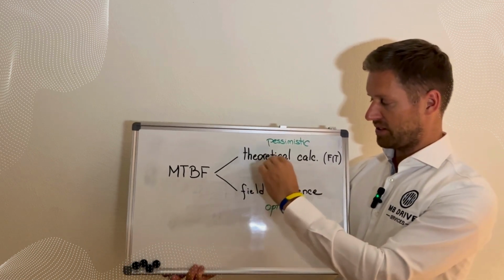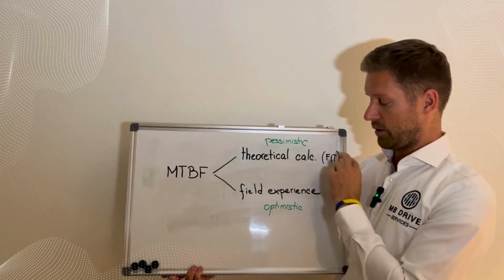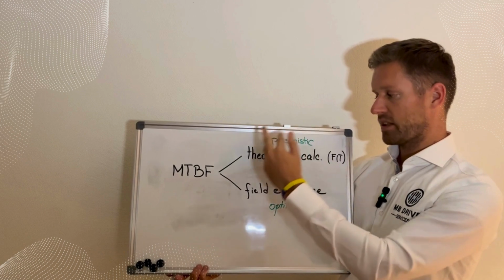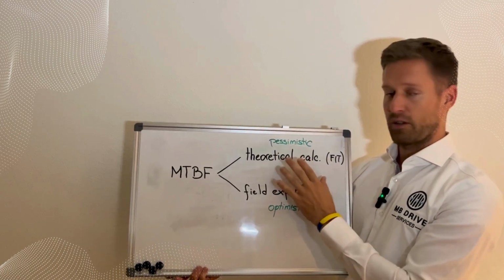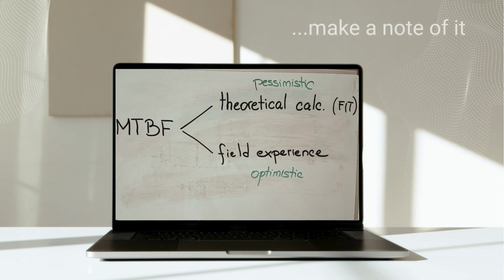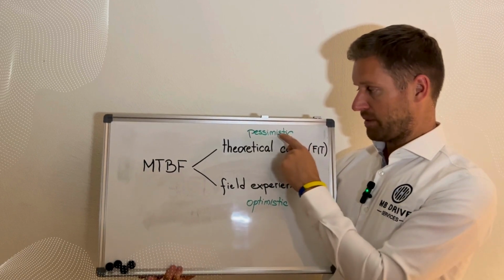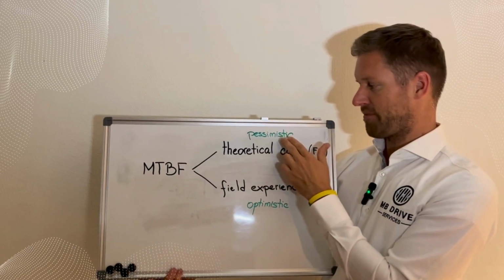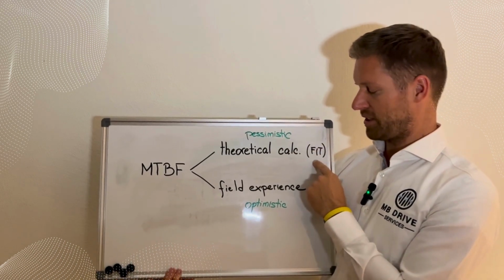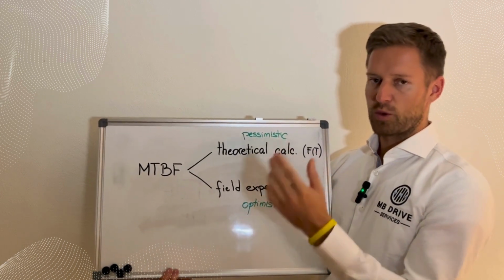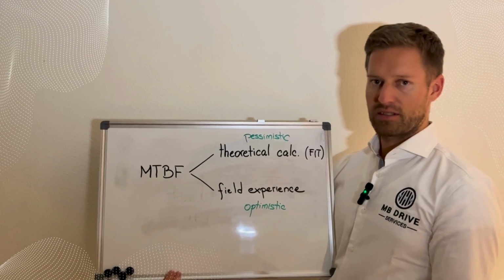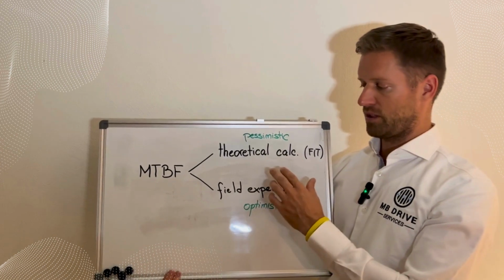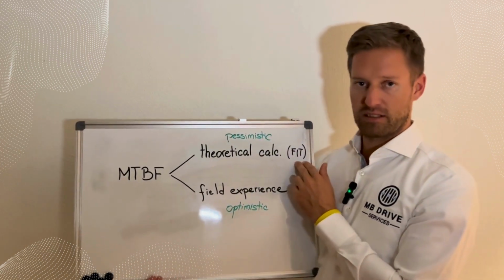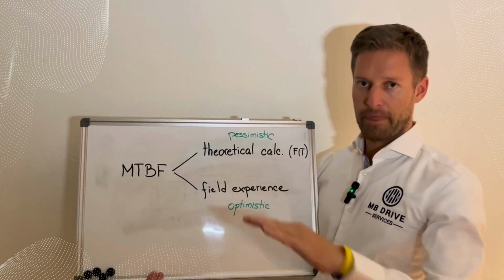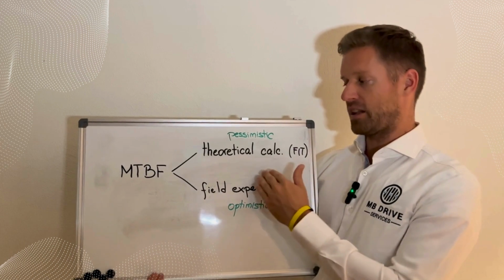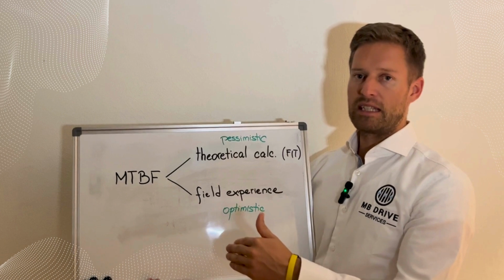You can take each single part inside the VFD, consider the FIT rate of that part, and calculate the overall MTBF of the VFD with this approach. This approach, in my opinion, is always a little bit pessimistic, because for the definition of the FIT, the failure in time, you consider operating conditions as design conditions, and the real conditions might be more favorable. For example, you consider 40 degrees Celsius ambient temperature continuously, whereas in reality it's specified up to 40, but maybe the average temperature is 20 degrees Celsius.